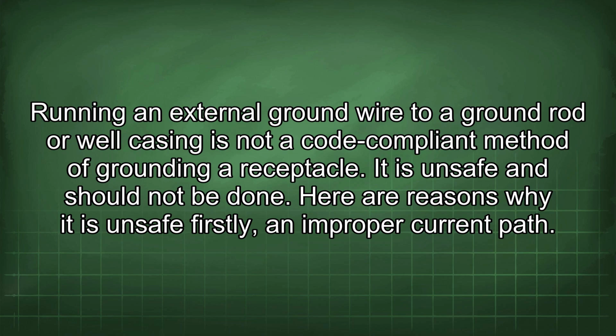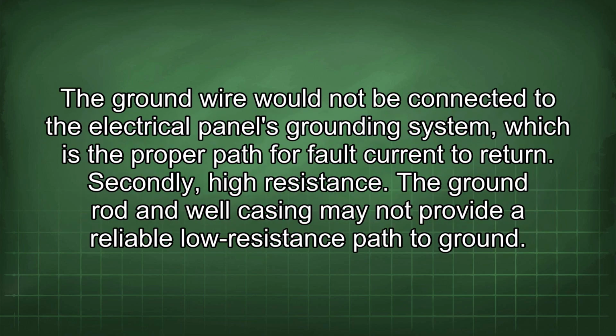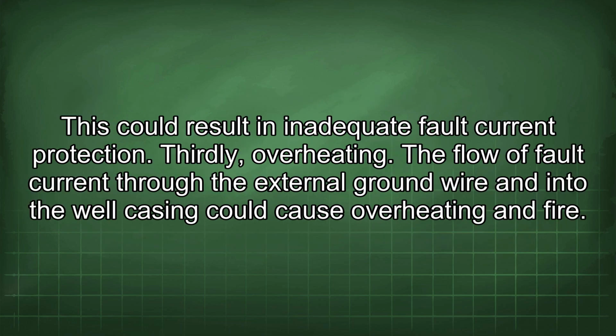Firstly, an improper current path. The ground wire would not be connected to the electrical panel's grounding system, which is the proper path for fault current to return. Secondly, high resistance. The ground rod and well casing may not provide a reliable low resistance path to ground. This could result in inadequate fault current protection.